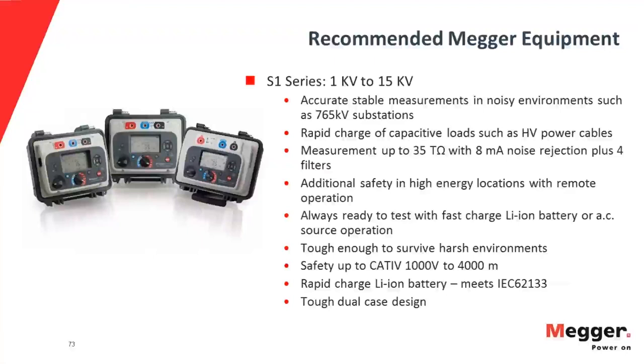These are the medium voltage testers that we offer, a 5, a 10, and a 15 kV unit. And these bullet points pretty much speak for themselves. You get high accuracy in very noisy environments. You get rapid charging because you could be on very large test equipment that has large capacitive loads, and so they can take a while to charge. So that speeds up your testing. You have a very high measurement range up into teraohms, thousands of gigaohms, which in turn are thousands of megaohms. And you have the highest degree of noise protection. You have your remote operation for operator safety, your battery protection, and a couple of the other bullet points there.